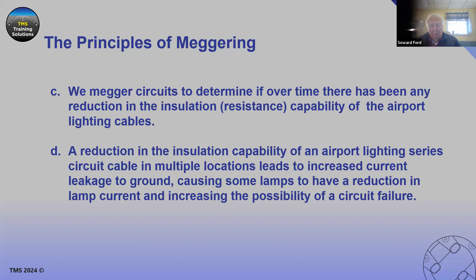The current from a megger is limited to just a few milliamps, 3 to 5 milliamps, low current, to prevent insulation breakdown. Lower cable insulation values will sometimes result in a lower than selected test voltage being applied in order to calculate insulation resistance within the restraints of available current. In other words, we've only got 3 to 5 milliamps, and we're using 1,000 volts, let's say, to measure the cable. It could be that we have so much leakage on that cable that all the 3 to 5 milliamps is going out, and the voltage then drops down because it is not able to do its job.